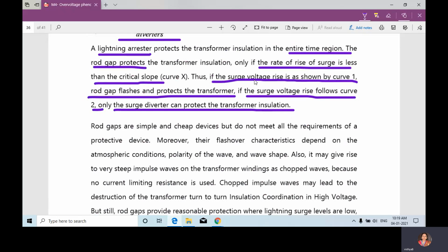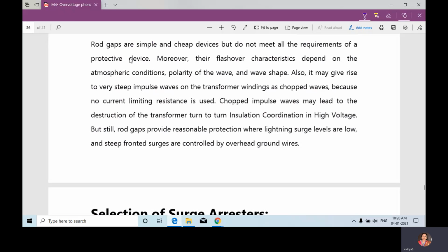They are saying that if the surge voltage rise is shown by curve 1, the rod gap flashes and protects the transformer. If that is the condition, then the rod gap will protect it. If the surge voltage rise follows curve 2, then the surge diverter can protect the transformer insulation. Next, rod gaps are simple and cheap devices but do not meet all the requirements of a protective device. It is low cost, but if you use it, we cannot meet all the requirements of a protective device.